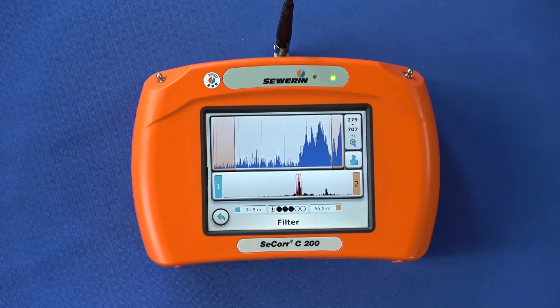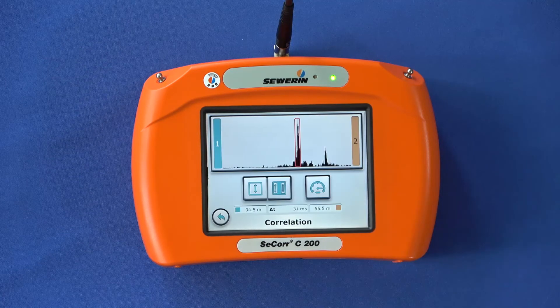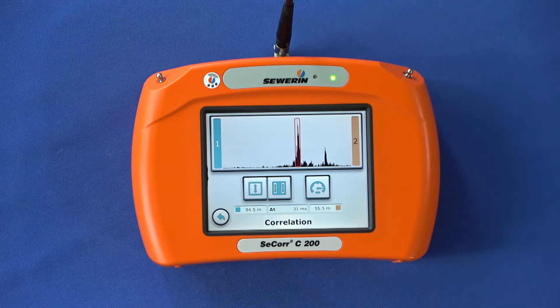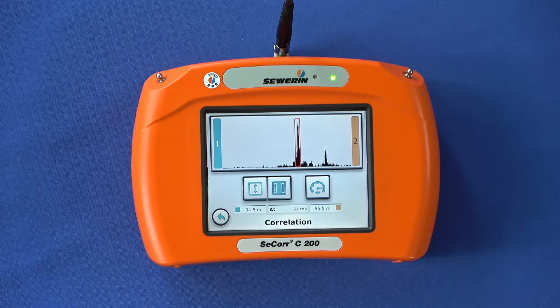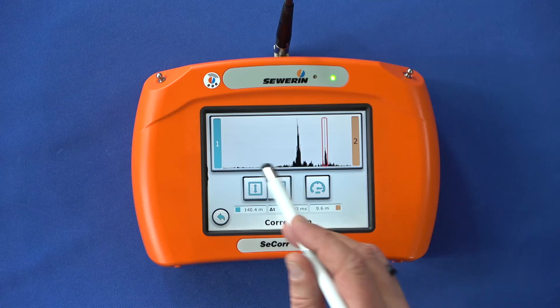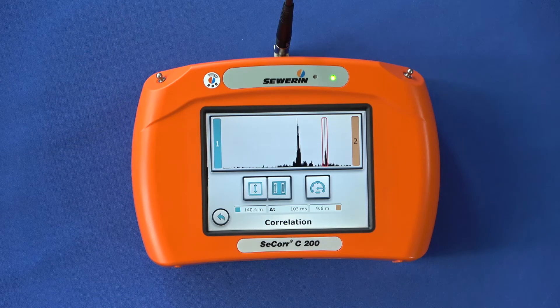If you want to make further improvements to your correlation result you can also use an extended correlation dialog. Tap the correlation function to open this extended dialog. You can now see the correlation function in the upper half of the display — this large display allows you to recognize smaller secondary peaks much better. You can set a mark by tapping in the correlation and you will immediately receive the associated data of the secondary peak in the results area. Two function groups lead to the optimization functions: peak suppression and sound velocity measurement. Peak suppression is very useful if you see two peaks in the correlation function and one of them matches the position of a known sound source — for example a pressure regulator.